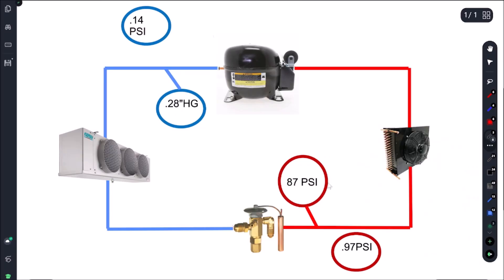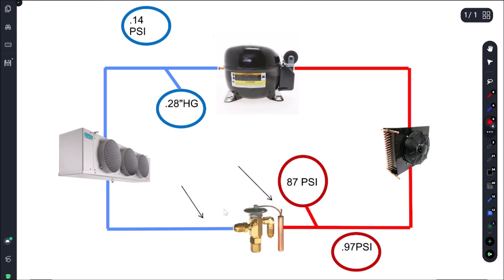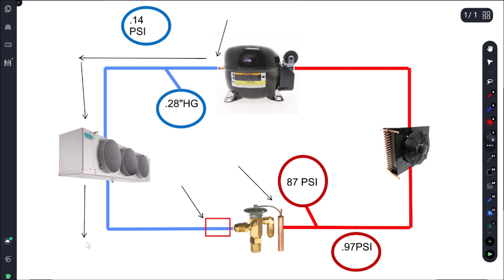All right, so we have a restriction in the system. What does that mean? It means that this cap tube here is most likely plugged or the filter dryer. So what I'm going to do is I'm going to sweat in a new filter dryer right here and I'm going to leave one end capped off. So that means this section right here of the cap tube is going to be open. I'm going to push nitrogen from the compressor here, which is going to flow it through this way. We're going to come through our evaporator coil and then we're going to come out here of the cap tube that I'm going to leave open. And our filter dryer is going to be capped off and we're going to keep pushing nitrogen through until it comes out of this cap tube.